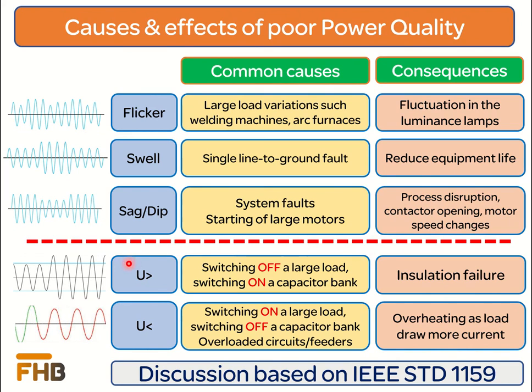Overvoltage is commonly caused by switching off a large load or switching on a capacitor bank. Overvoltage can cause severe damage in the power system such as failure of electronic devices. Sustained overvoltage drastically reduces the life of electrical equipment such as transformers, cables, capacitor banks, and electrical motors. Events causing undervoltage are simply the reverse of the events which cause overvoltage. Overloaded circuits or feeders can also suffer from undervoltage. Long duration undervoltage increases heating loss in electrical equipment, and motor controllers also drop out during undervoltage conditions.